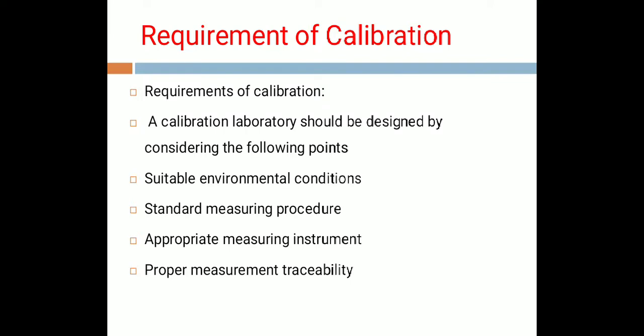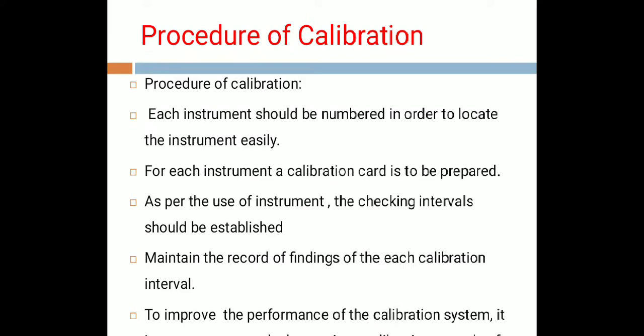Requirement of calibration. Why is calibration required? A calibration laboratory should be designed by considering the following points: suitable environmental condition, standard measuring procedures, appropriate measuring instruments, proper measurement traceability. Procedure of calibration. Each instrument should be numbered in order to locate the instrument easily. For each instrument, a calibration card is to be prepared. As per the use of the instrument, the checking intervals should be established. Maintain the record of findings of each calibration interval to improve the performance of the calibration system.